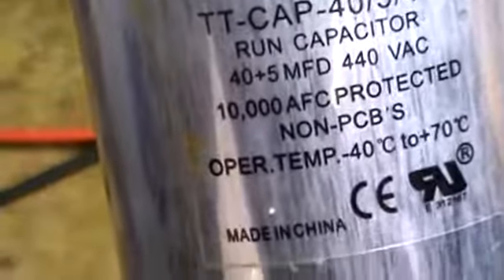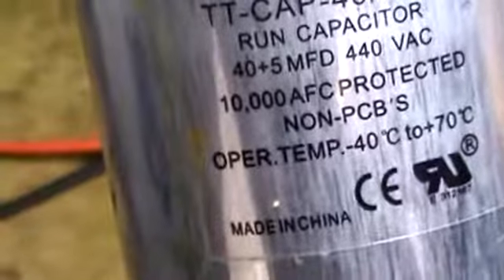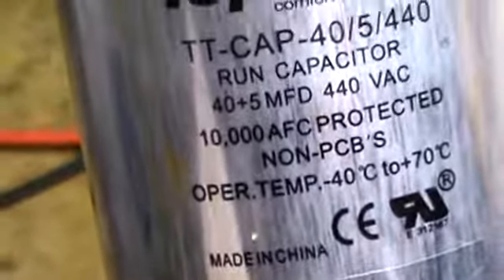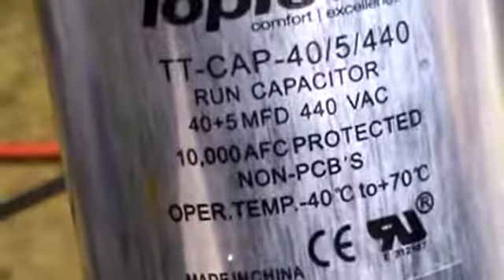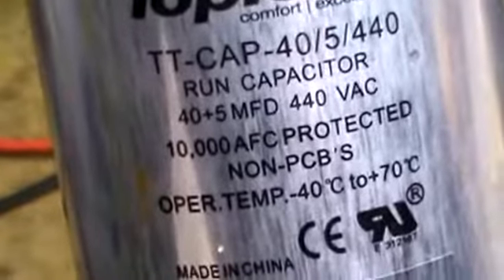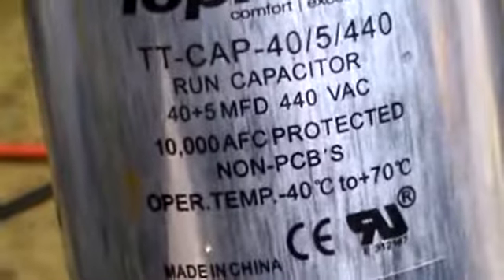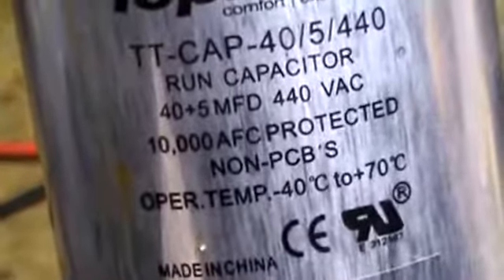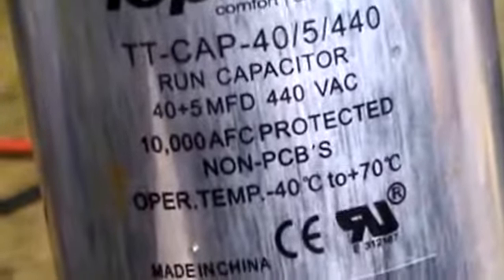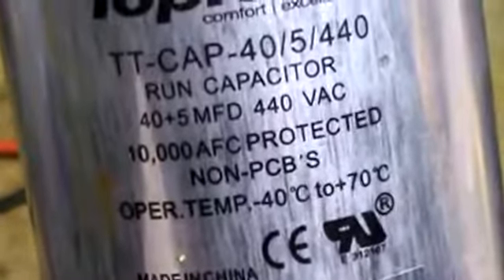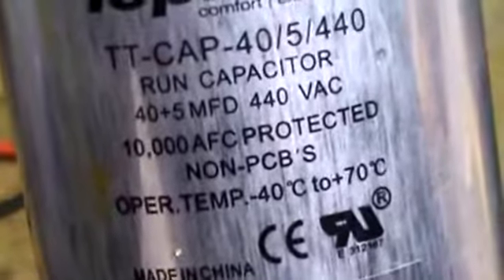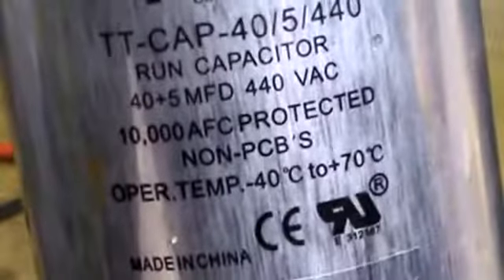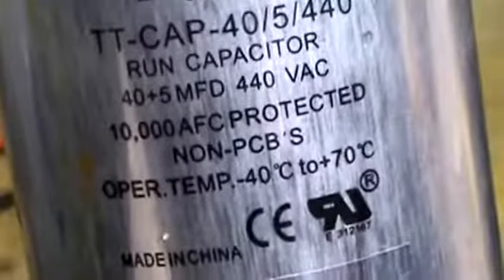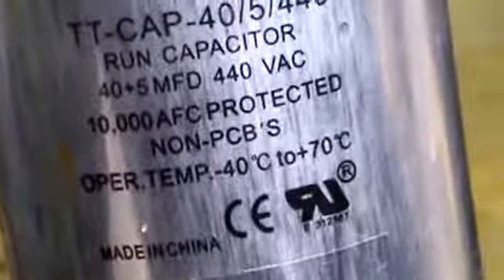Well, I removed the capacitor so that we can see how this is done just a little bit easier. First thing you want to do is to verify what value this capacitor is. This is a dual capacitor, and it's a 40 plus 5 MFD, which stands for microfarad. So the 40 is for the compressor side, and the 5 is for the outdoor fan motor side.